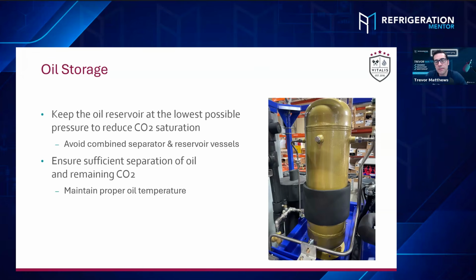We had some flooded tests with PAG oil, and I just couldn't detect the oil properly. I was also at the limit where the PAG oil started to flow up, and I've seen liquid CO₂ getting refilled into the compressor. But as it was at the same pressure as the suction pressure, with just a little height difference, it didn't boil off right away. So you could actually see the liquid CO₂ flowing around on the oil inside the crankcase. I haven't seen that in the field yet, luckily, because it's okay to do that in the lab. It's not very hard. Yeah, exactly.